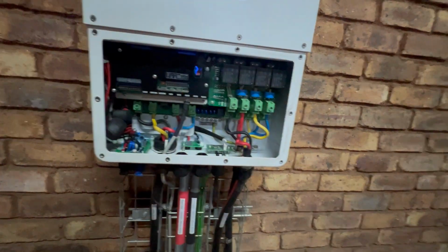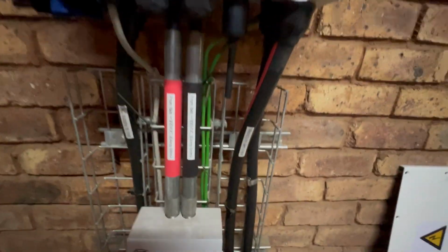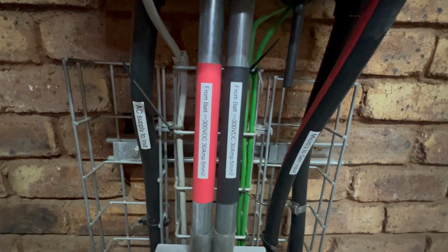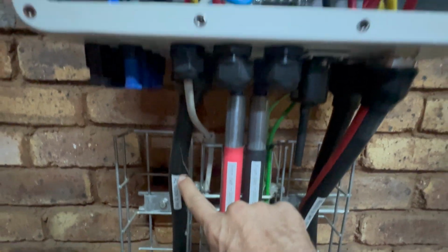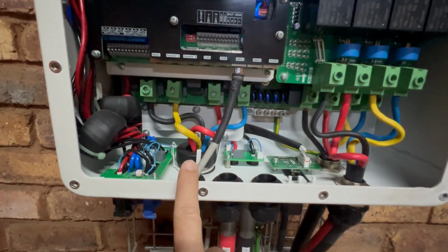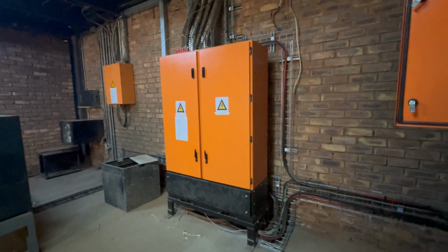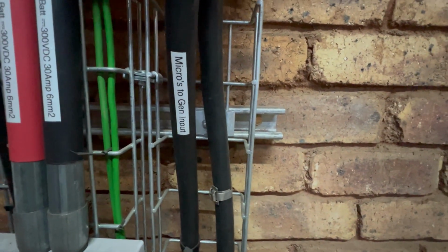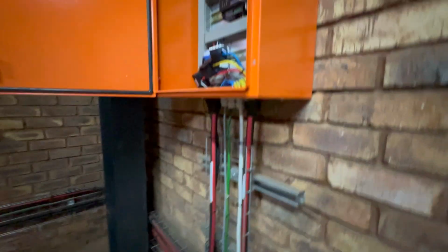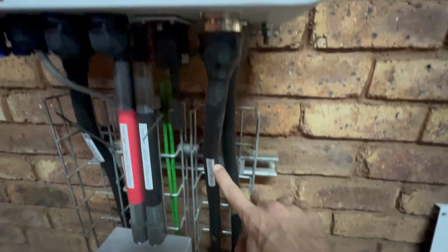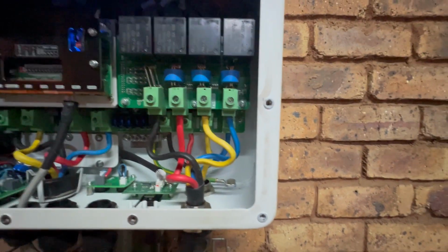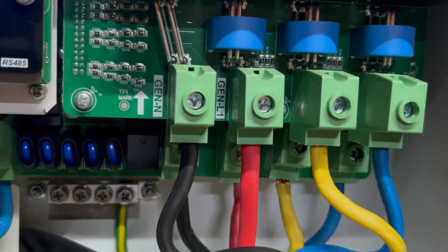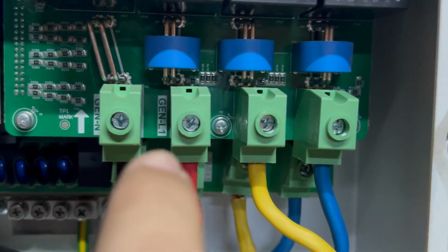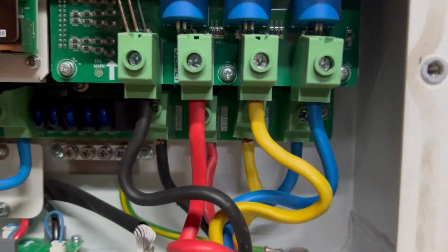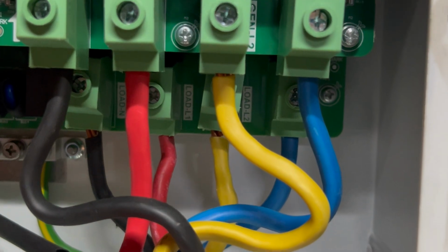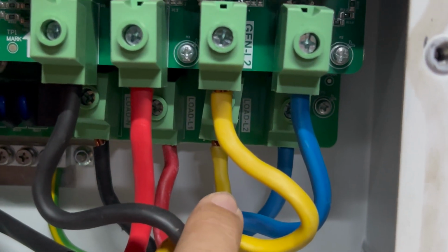Cool. If we take the cover off and we look at the labeling at the bottom over here, we'll see AC supply to inverter. That's the cable sitting over there. This AC supply comes all the way from that board. Then over here we've got the micros to gen input. So this is the cable coming from that board, comes all the way in, connected to the front. If you have a look at the labels, it shows right there, it shows gen neutral, gen line 1, gen line 2, gen line 3. And then the load for the inverter sits on the cables all the way towards the back.